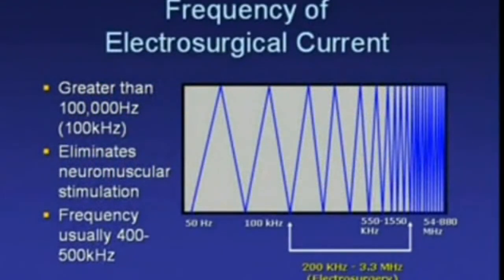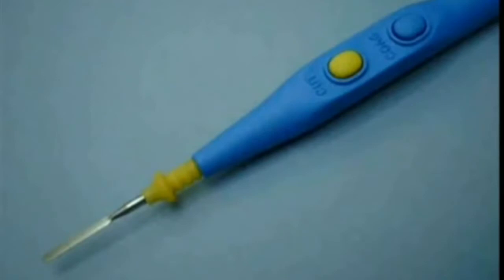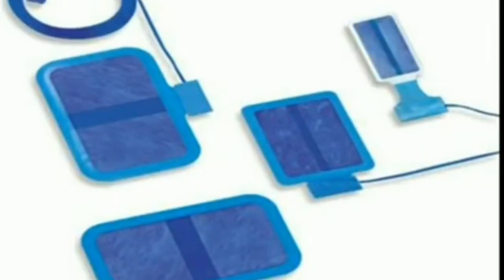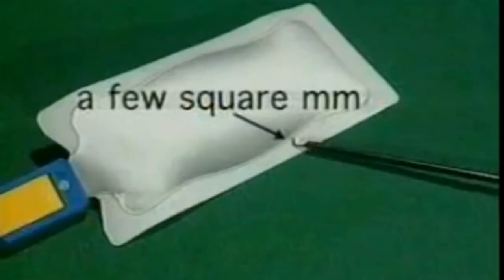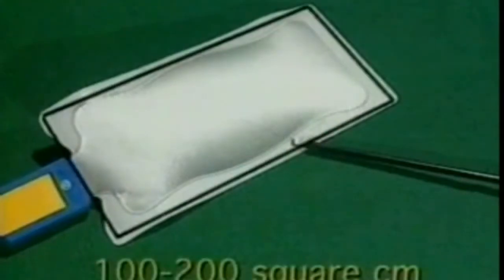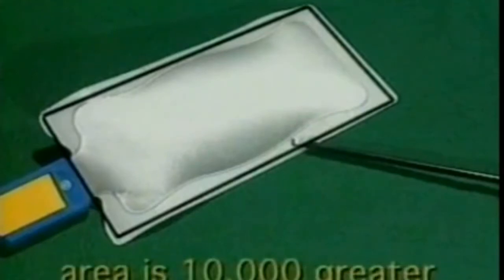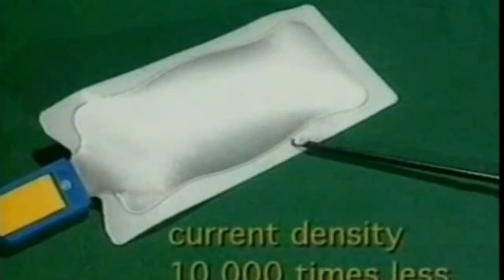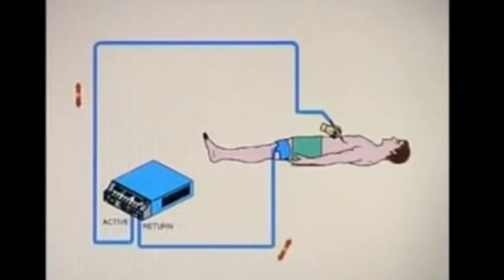Having established that the high-frequency AC prevents neuromuscular stimulation, why is the clinical effect achieved at the tip of the instrument and not at the patient return electrode? This comes down to a simple matter of surface area and current concentration. The power is concentrated over a tiny surface area at the tip of the electrosurgical instrument, yet dissipated over an area many thousand times greater at the patient return electrode, thus causing a negligible heating effect. It is important to appreciate that, despite what many think, the pad or patient return electrode does not earth the patient. The pad merely completes the circuit back to the electrosurgical generator. It is not an earthing device.